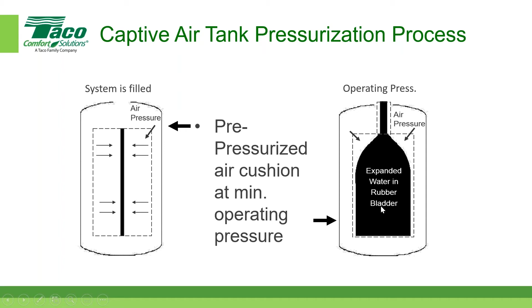Anyways, here's a pre-pressurized air cushion. On the left-hand side, as the system's filling, there's just an air cushion in there. Then under operating pressures, the water expands into that rubber bladder, and the air pressure holds it as much as it can. That's the pressurization process.